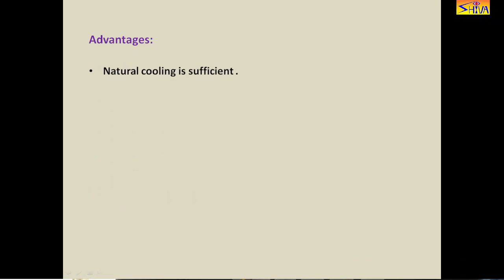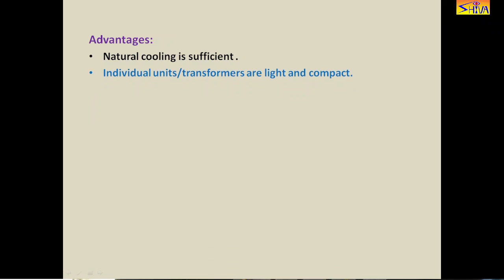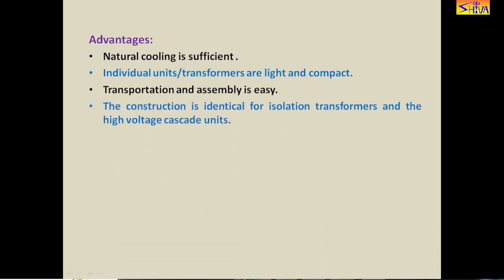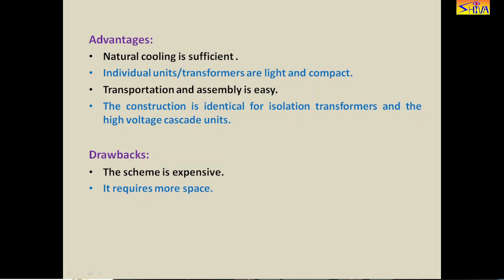The advantages of this scheme are: first, natural cooling is sufficient; second, individual units are light and compact; third, transportation and assembly is easy; fourth, the construction is identical for isolation transformers and the high voltage cascaded units. The drawbacks are: first, the scheme is expensive because separate isolation transformers are needed; second, it requires more space because in addition to the cascaded transformers, isolation transformers are also required.